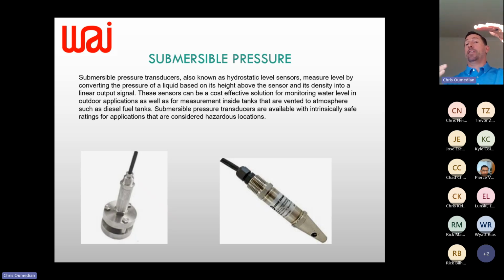So you basically create a table. This is an inexpensive way to get an analog output on a level. As that goes up and down, you create a table that says if my pressure is X, my tank level is Y. Does that make sense? Any questions on pressure or guided wave radar?